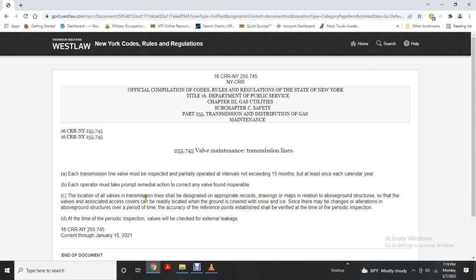So the valves associated with the covers can be readily located when the ground is covered with snow and ice. Since there may be changes or alterations of the above ground structure over a period of time, the accuracy of the established reference point should be verified at the time of the periodic inspection. At the time of the periodic inspection, valves should be checked for external leakage.